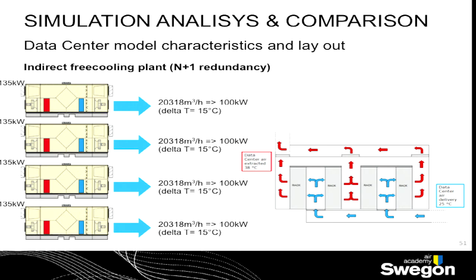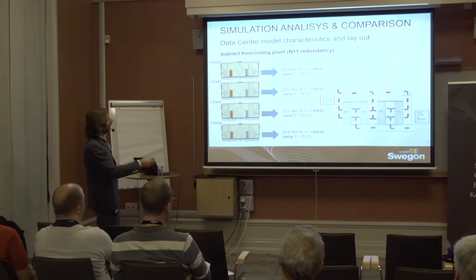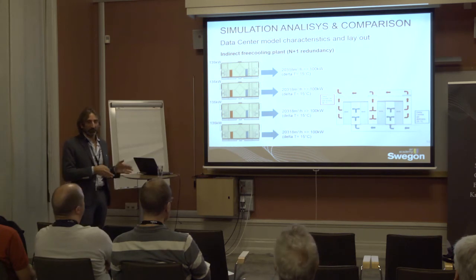In this case, we are extracting air at 38 degrees and we are delivering air at 25 degrees. So we are totally compliant with the ASHRAE conditions because we are allowed to deliver air up to 27 degrees, but we take a margin. So we are delivering at 25 degrees with a delta T of 13 degrees. When you consider an air free cooling system, it is always important to look at the delta T, because on the delta T is based, of course, the airflow of the system and the energy consumption.